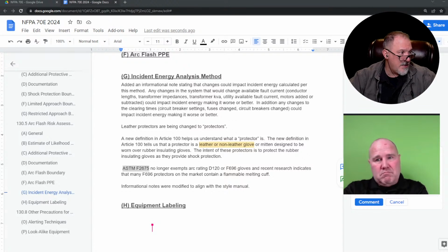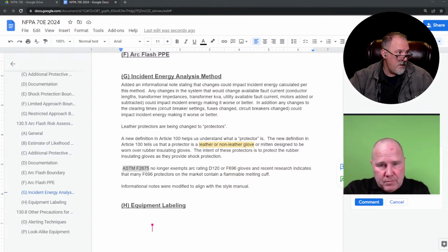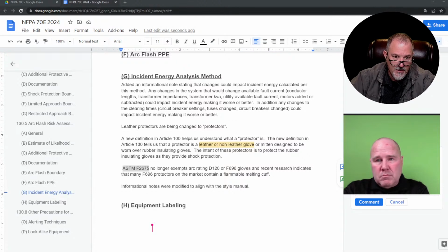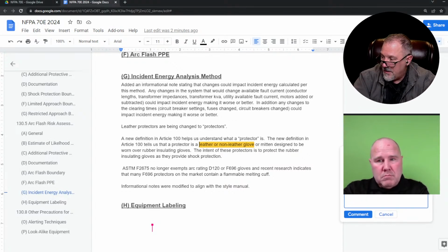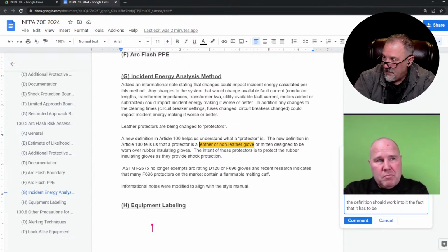Look, this says ASTM F2675. It says arc flash, glove testing. So glove testing to the ASTM F2675 standard test method for determining arc ratings of hand protective products developed and used for electrical arc flash protection is performed to determine the arc rating, ATPV or EBT, of a glove. So really, to your point, the definition should work into it the fact that it has to be listed, maybe, or have an arc rating.